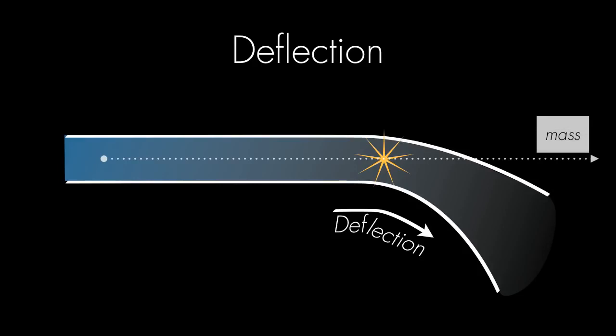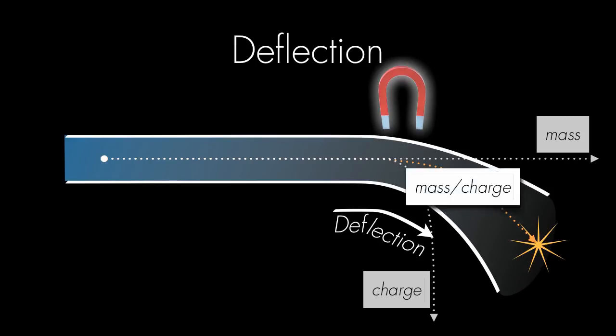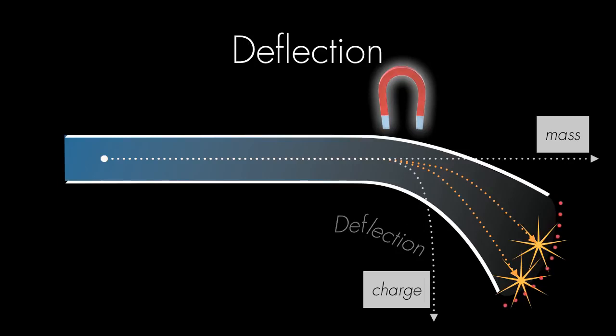However, in a mass spectrometer, we use electromagnets to try to deflect the ions off their path. The amount of force that the ion feels from the electromagnet is proportional to its charge. The path that the ion actually takes is a result of its mass-charge ratio. A different particle with a different mass-charge ratio will take a different path. And this is what we are actually detecting: different mass-charge ratios.